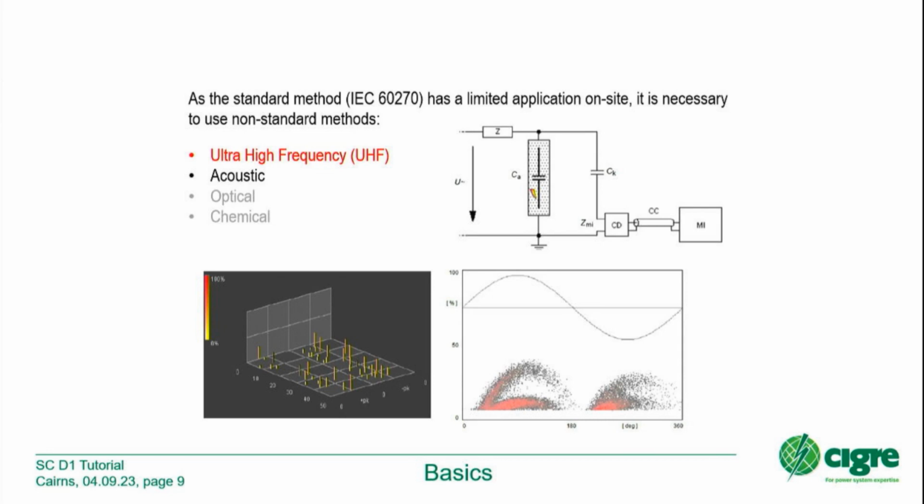For example, this is a rabbit-like pattern from a void in epoxy. Here, this is the back of the rabbit, and this is the long ear of the rabbit. This expression was introduced by some Japanese experts in the 1990s, so everybody knows that as a rabbit-like pattern.